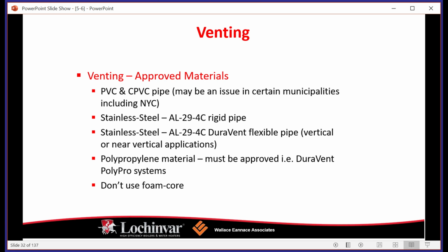And polypropylene. Okay, what is polypropylene? If you haven't seen polypropylene, it's typically called polypro. It's going to be like a dark gray or almost black looking pipe. And again, this is a plastic material pipe that is significantly lighter. It's going to be more cost effective than AL29-4C. The advantage of polypropylene is that it does not burn and create toxic gases.